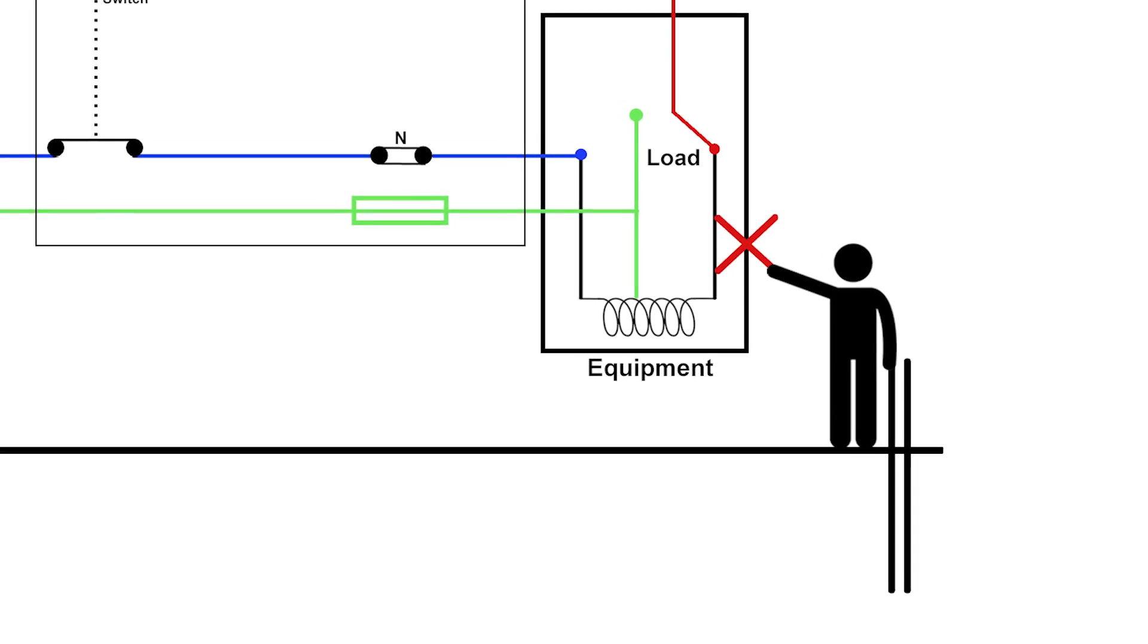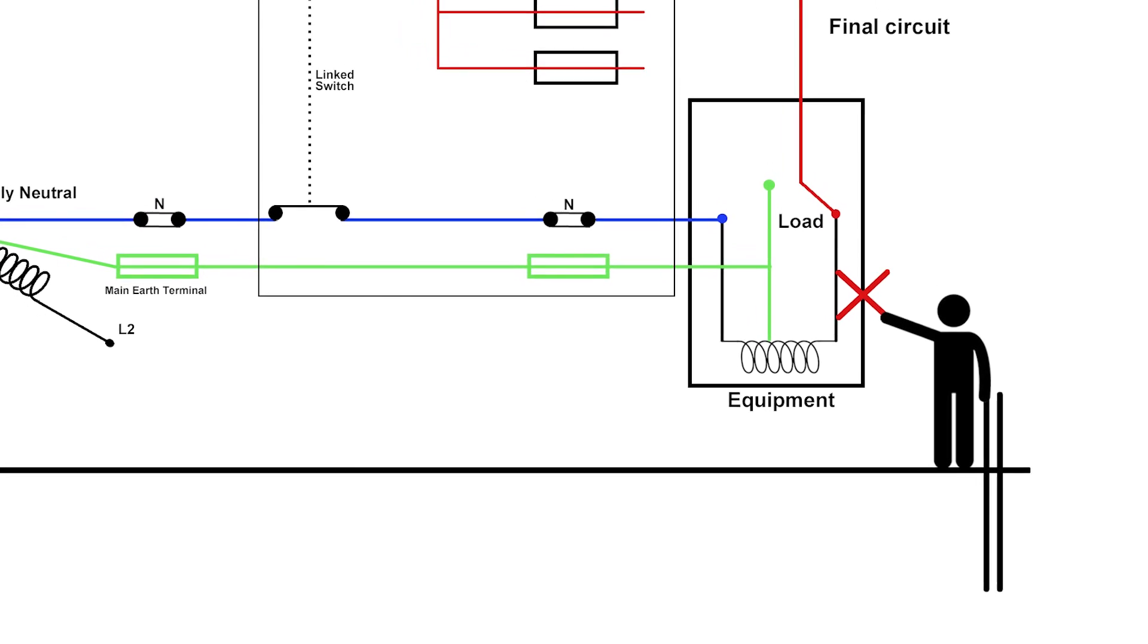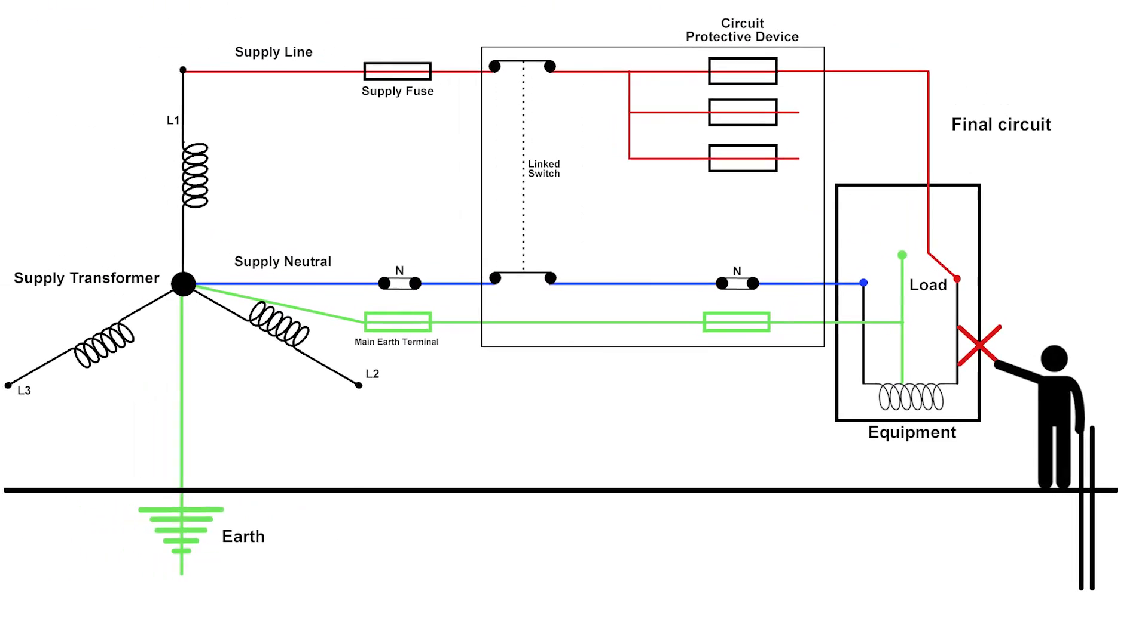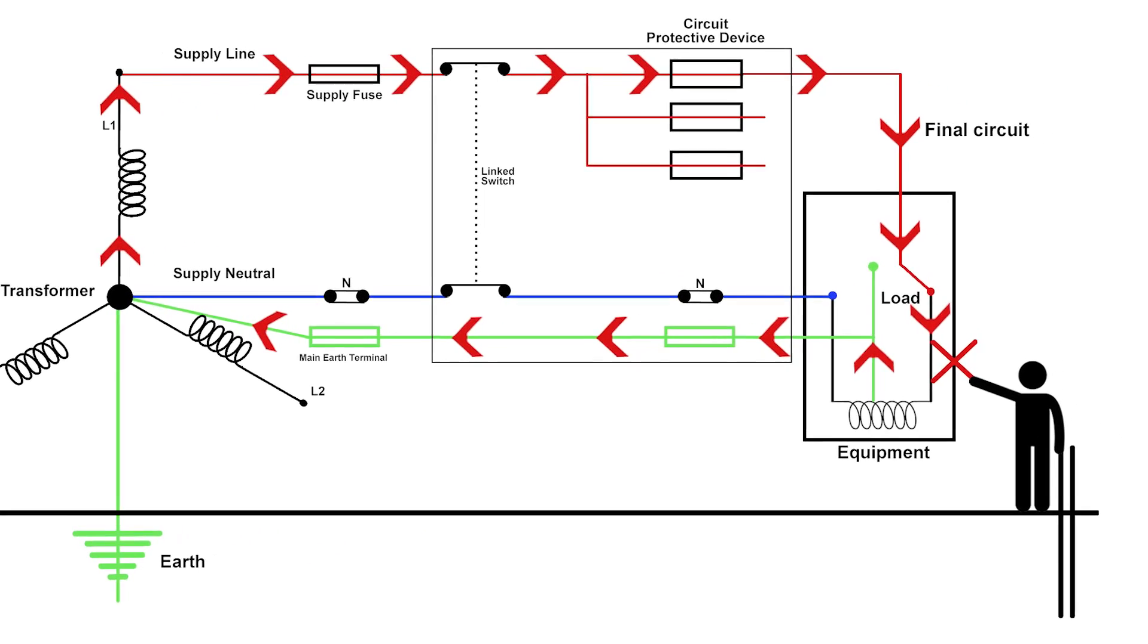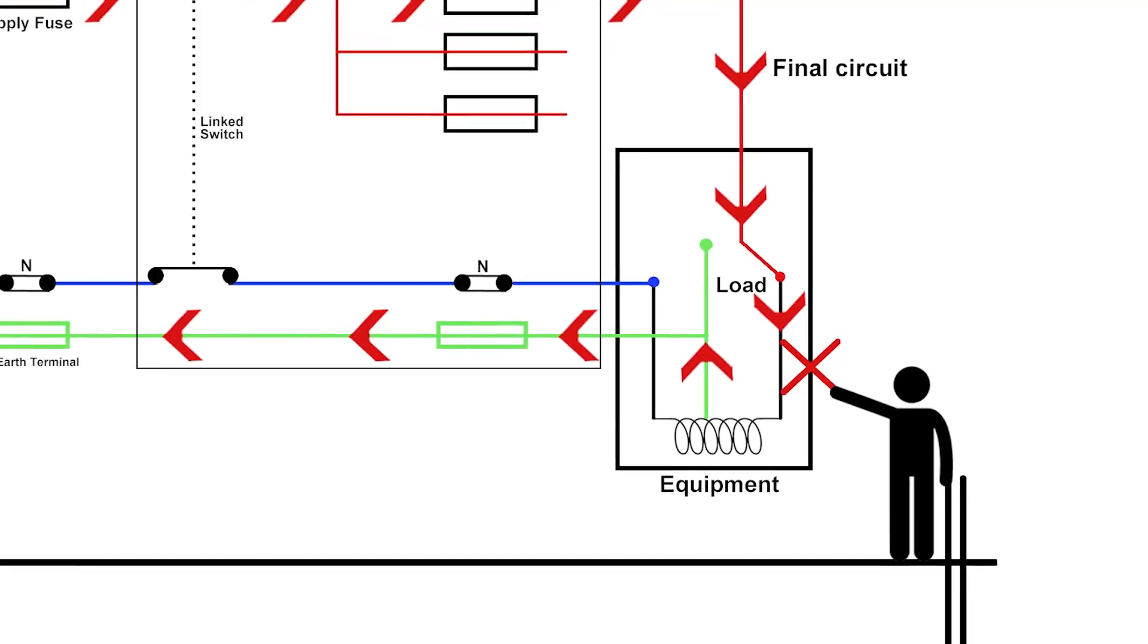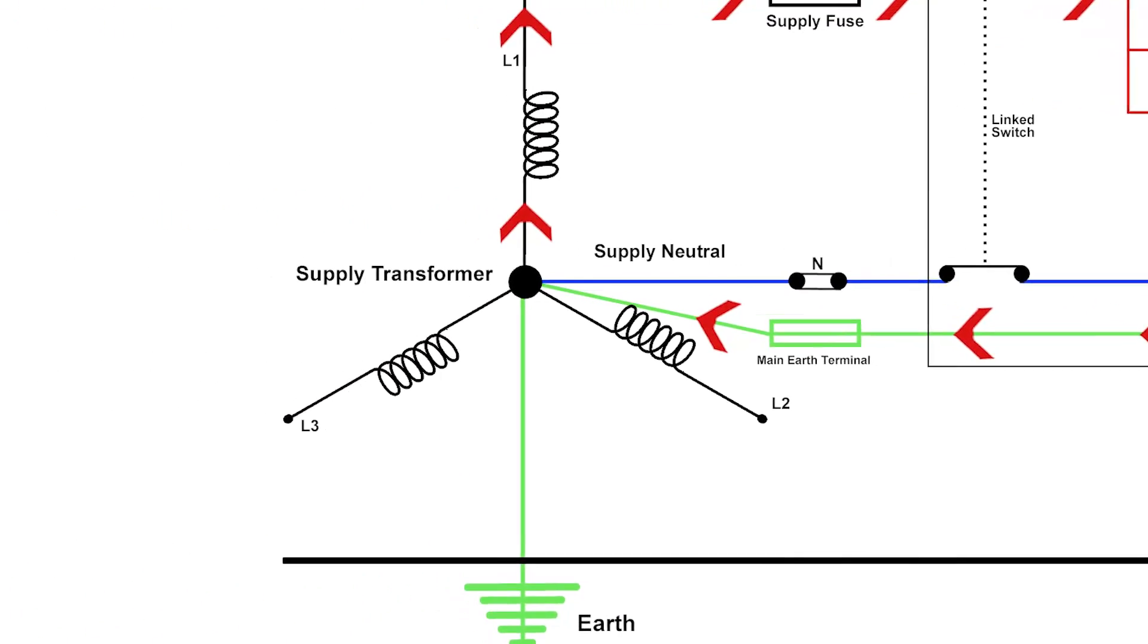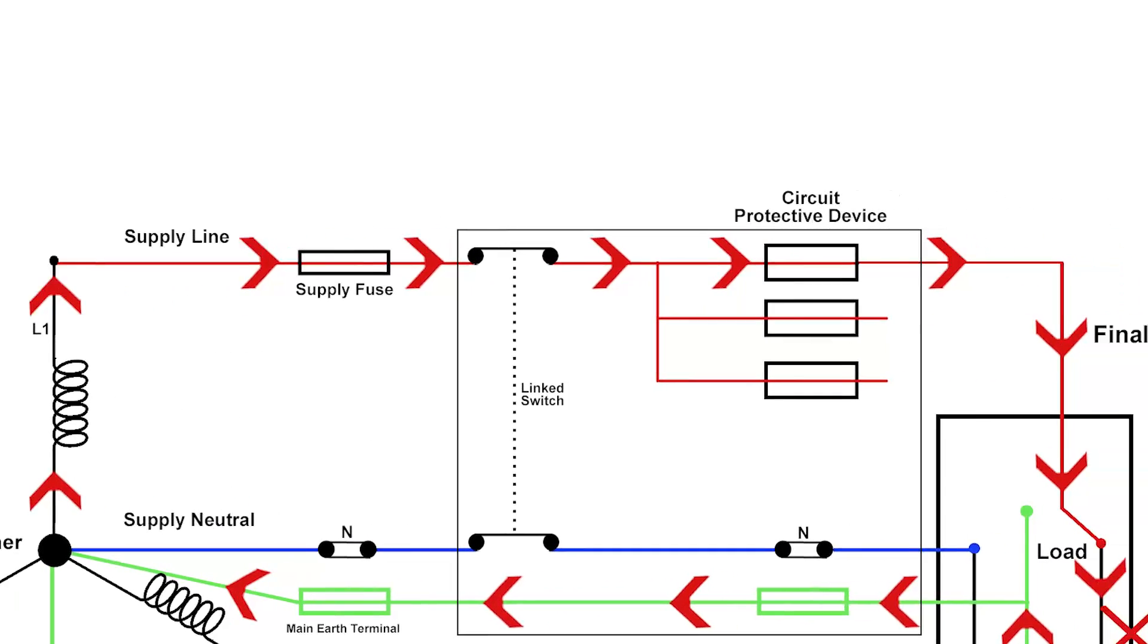It's important that my earthing system has a low enough resistance so that enough current can flow to operate this protective device. You can see that in the event of a fault, the current's going to flow through the case of the machine to wherever our earth is connected, then through our earthing system back to the star point of the transformer, and it forms what we call an earth fault loop.